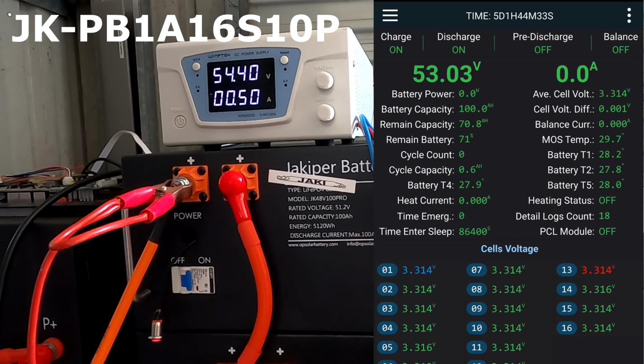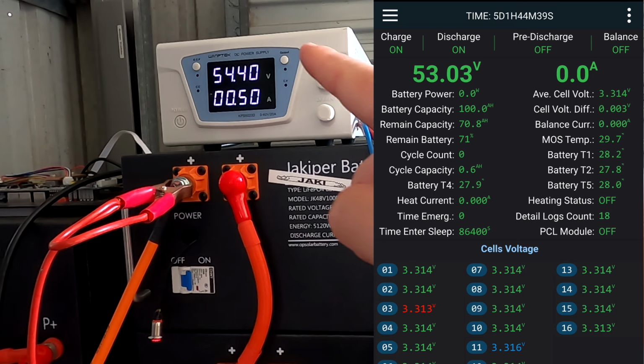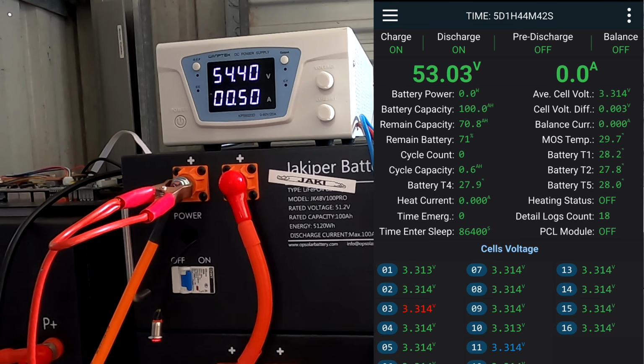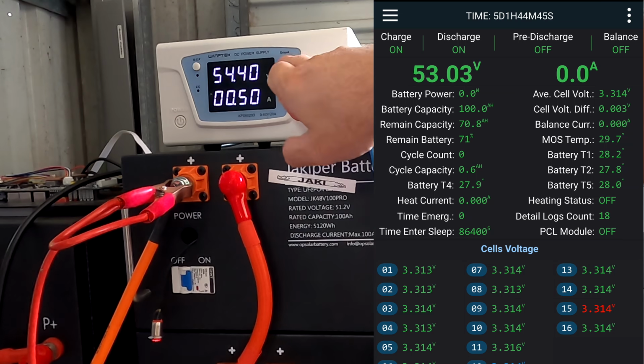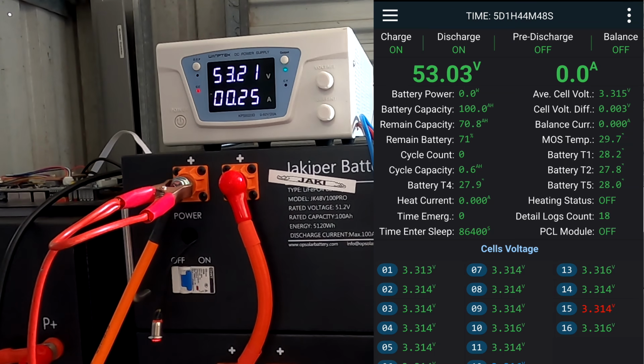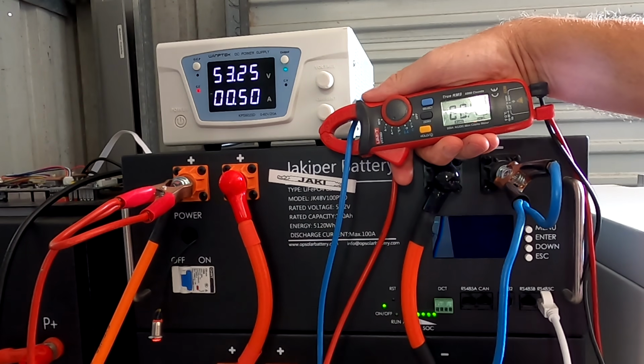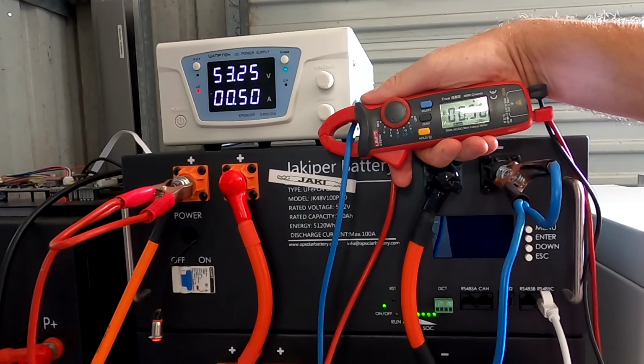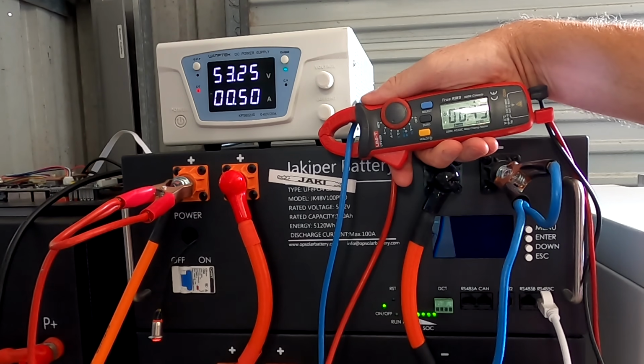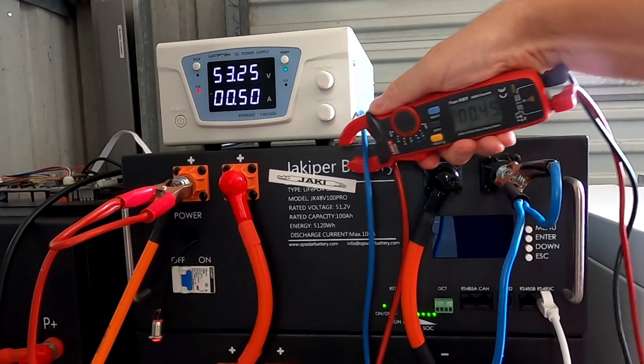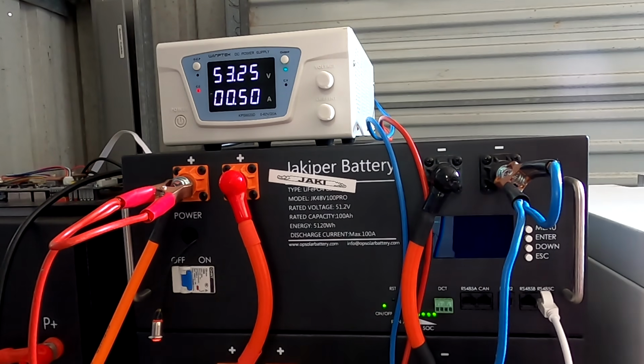We are starting with the 100 amp BMS here in the JK battery. I have already connected the power supply, and we are starting with 500 milliamps of charging current into the battery. Okay, let's turn this on. And you can see 0.2. Let's check on the current. Yeah, I can measure 0.5 amps here as well with my clamp meter. So I guess the power supply and my clamp meter are correct, and the JK is just not calibrated for these small currents.